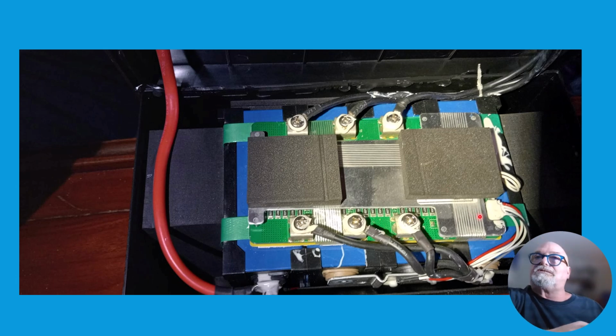The other thing that I don't like about this construction, let's take a look at the pads first. Again, this is a 200 amp BMS, and this is where each of these wires goes to the outside of the case here, and they all go into one terminal up top, just like they do down here. You can see they got 3 wires stuffed into one terminal on the battery negative side, and then they divide out into 3 on the printed circuit board of the BMS.